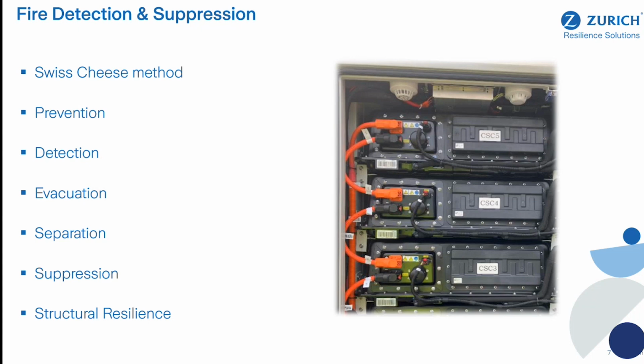Evacuation. So if bad things are happening inside a battery container, we don't want those gases building up in there. You'll see a picture on the next slide, I think, where the actual build-up of the gases can be quite dramatic. This is basically a venting system in the roof of the containers. They will open if these gases are spotted by the detection systems, and it will clear it all to prevent explosions and the likes.